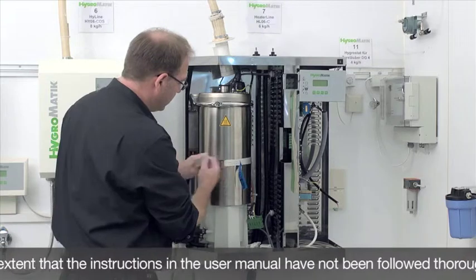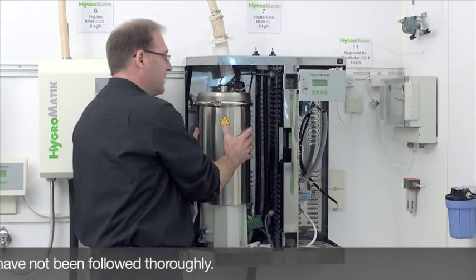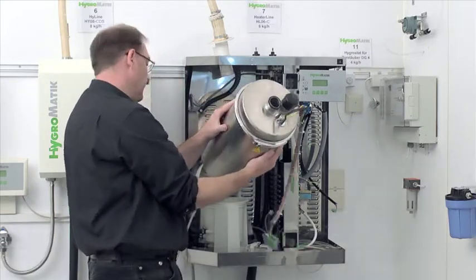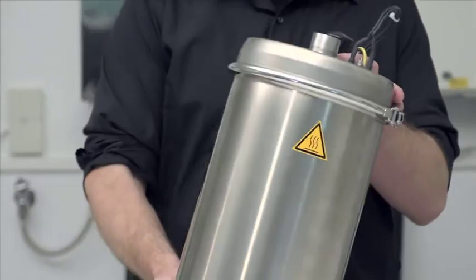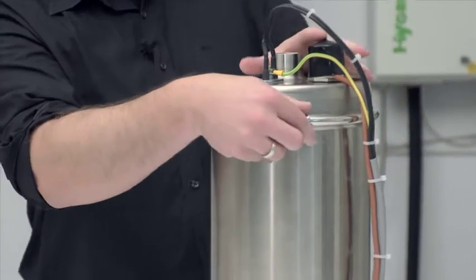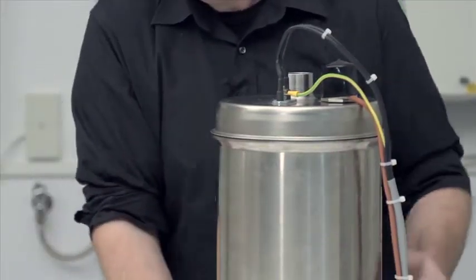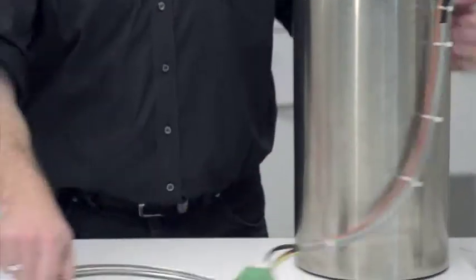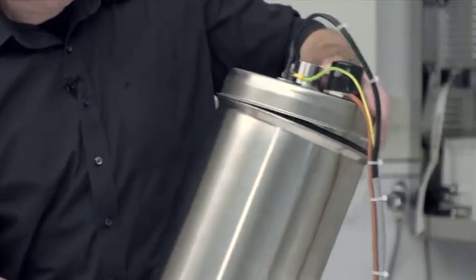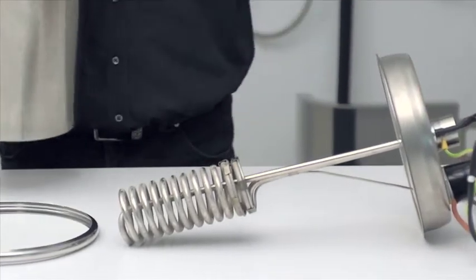Next I unfasten the cylinder clamping belt and now I am actually ready to lift the cylinder out carefully. For cylinder maintenance we open the cylinder on top at the clamping ring. Then we can pull up the cylinder top and have the heating element out as well which is connected to the cylinder top.